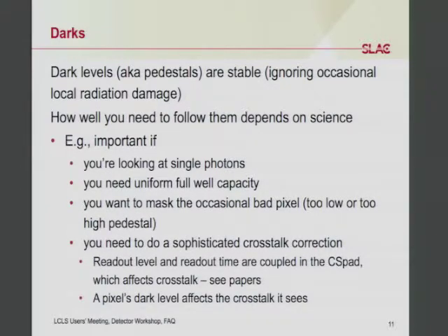But you shouldn't wait too long because you always have the thermal drift anyway. And you should take a dark anytime you change settings or something. The environment matters as well. At CXI, if you're under vacuum and the detector has been sitting there for 3 days, as Garth always asks us to make sure we get the camera in time for him to do, then it should be more stable.